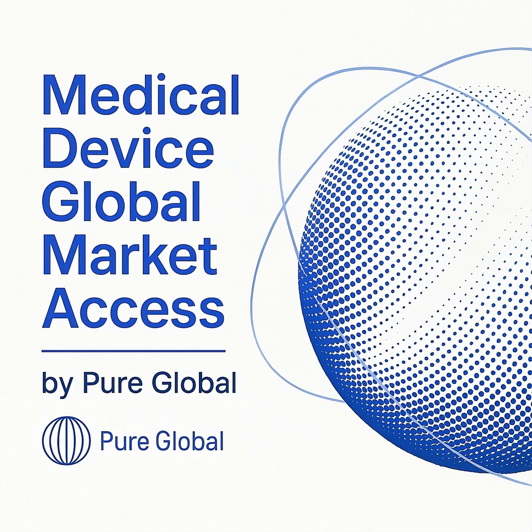A conformity assessment must be conducted, which, for higher-risk devices, involves a notified body. Following a successful assessment, an EU Declaration of Conformity is drafted, and finally, the CE mark can be affixed to the device and its packaging. It's important for manufacturers based outside the EU to appoint an EU-authorized representative. Once a device is CE marked, it can generally be marketed across all EU member states without needing additional national approvals.